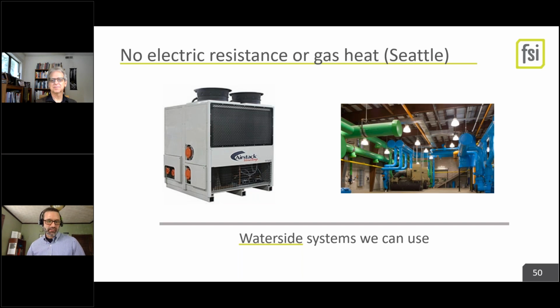So if you're doing water side systems, not necessarily direct heat pump, you can use heat recovery chillers, which we talked about for efficiency a bit there. That's what's on the left. On the right is your regular centrifugal chiller, but there's some great heat recovery potential off of that if you go looking for them for your 4-pipe heating supply return, cooling supply return. So putting heat pumps even in your central plant-based systems, if you're doing water side, still goes a long way towards avoiding gas.